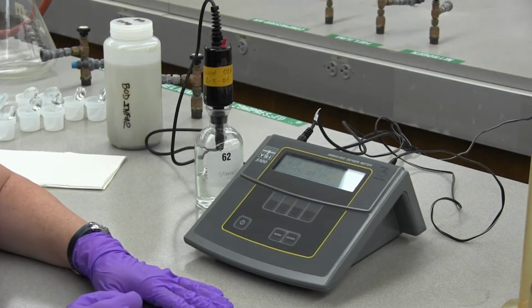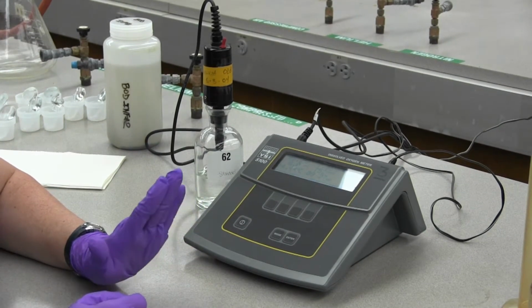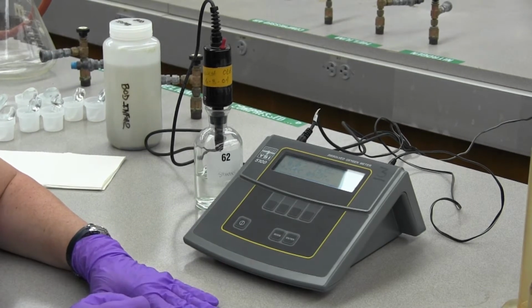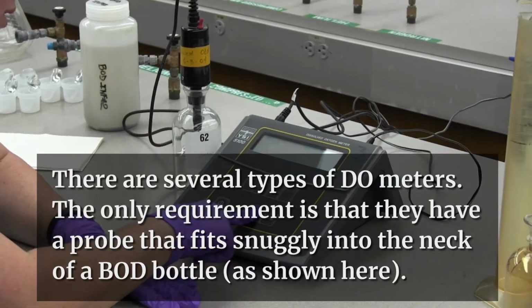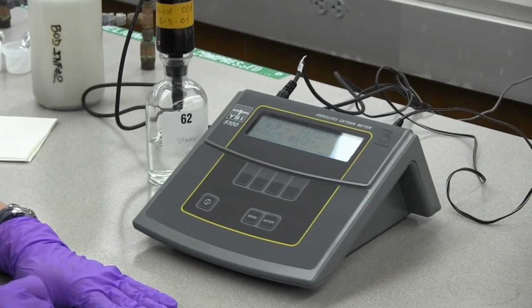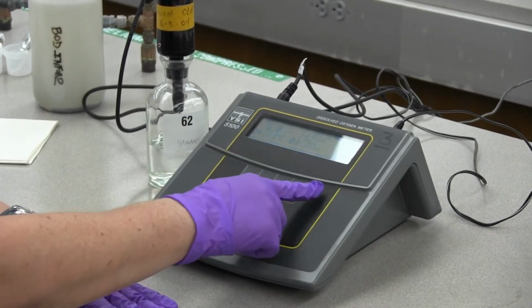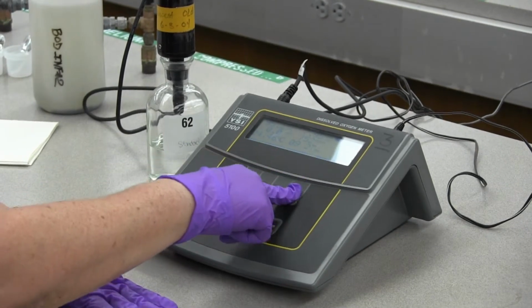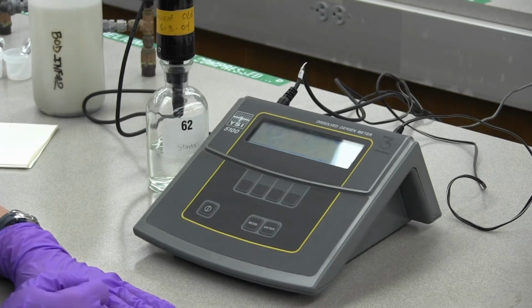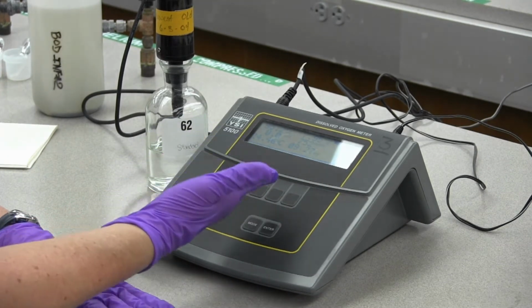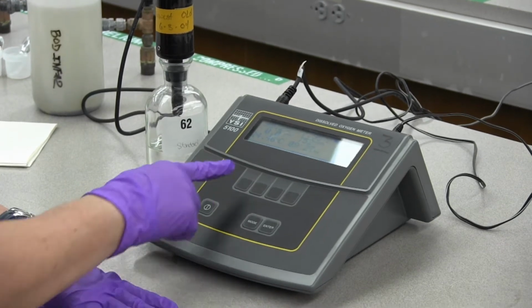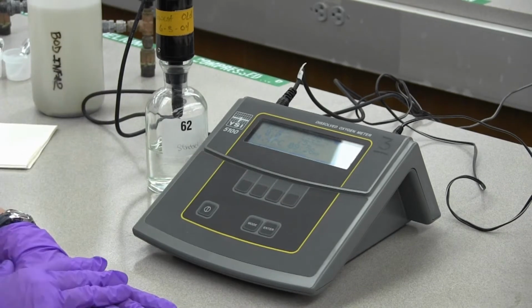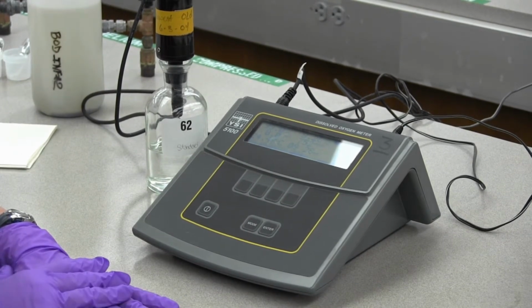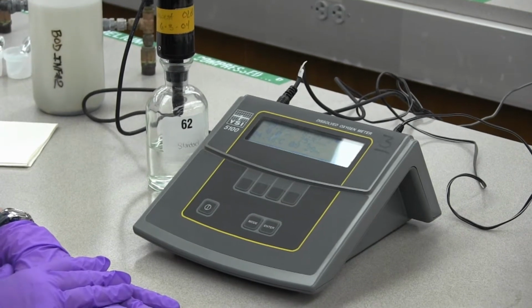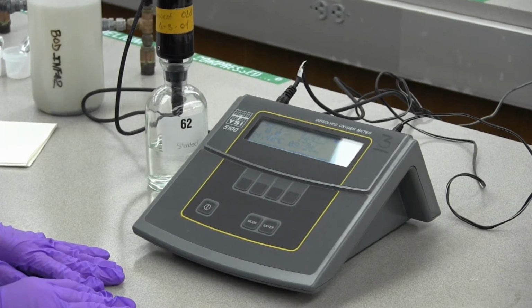And that's what we're going to do first, is calibrate the meter. And you can just calibrate according to your manufacturer's instructions that come along with the meter. What I'm going to do here is get back to the main mode. Okay, I am at the main mode now for the display. I'm going to press the soft key that's right up under calibrate, and it gives me a choice of auto calibrate, DO cal, that's the manual calibration, and I'm going to press the soft key under auto cal, and it says DO calibration saved. Okay, and now I am ready for the next step in the BOD test.